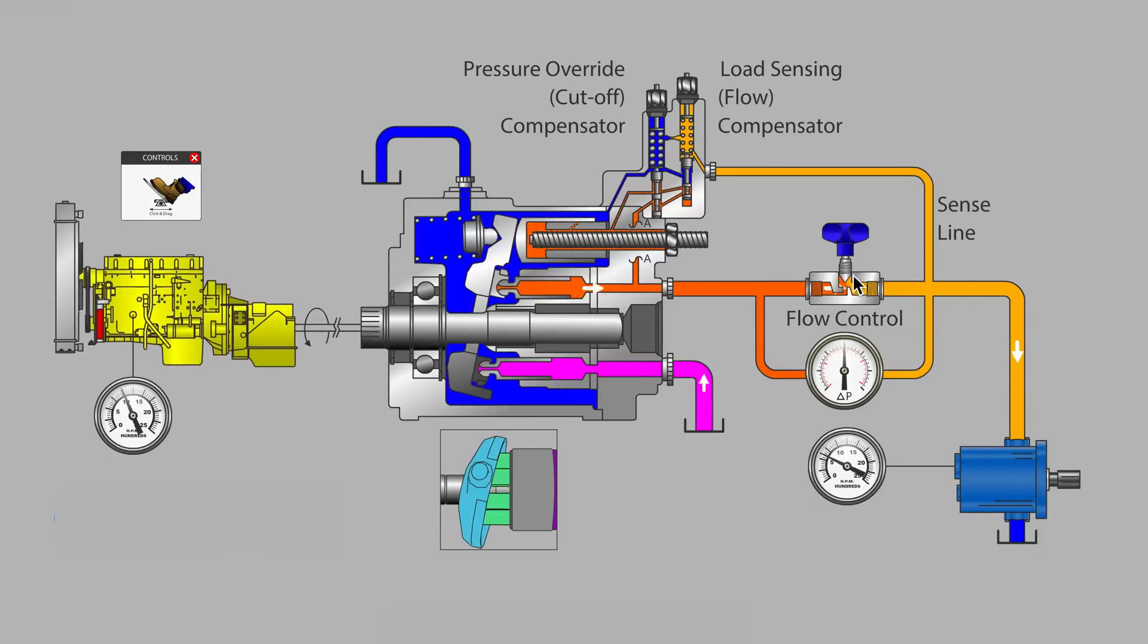But only for a brief moment. And the reason that it only happens for a brief moment is tied to what happens on the internal passage from the pump outlet over to the load sensing compensator.